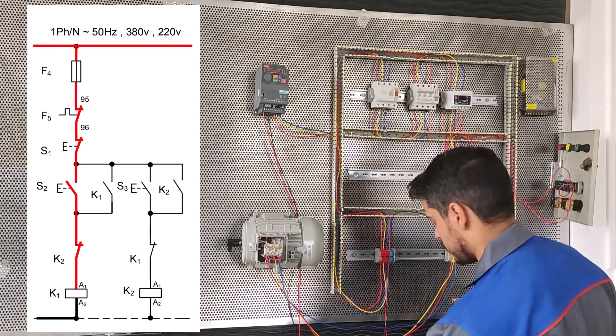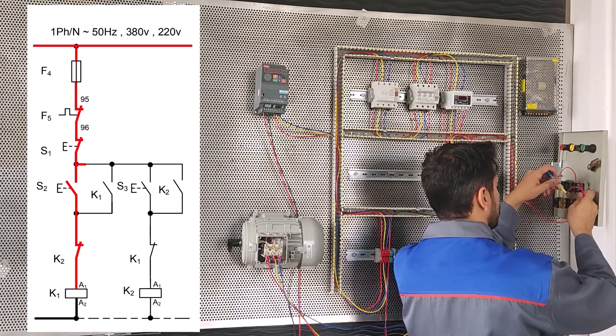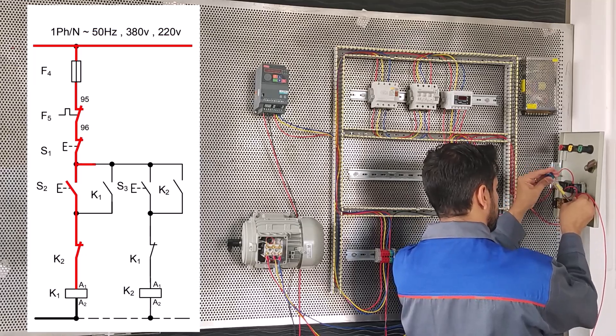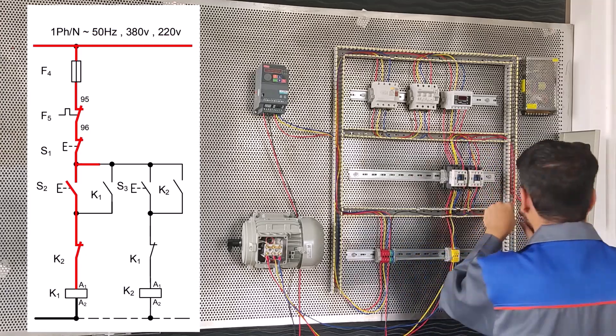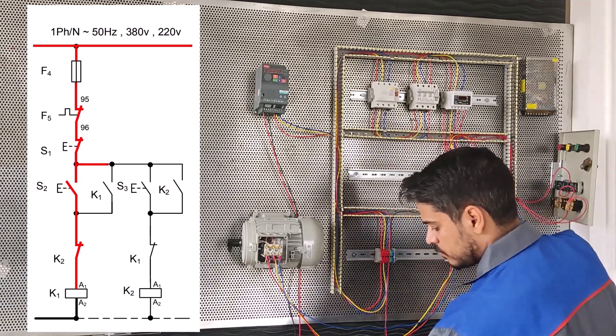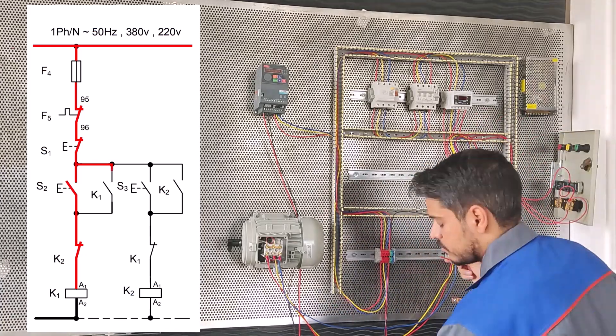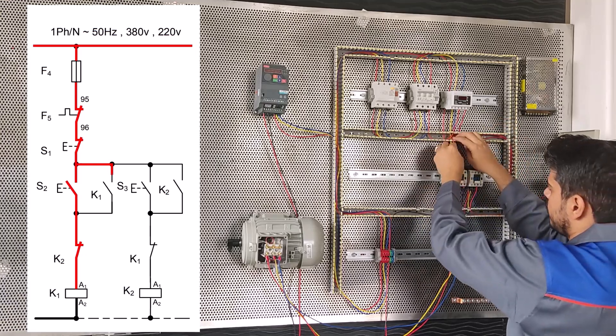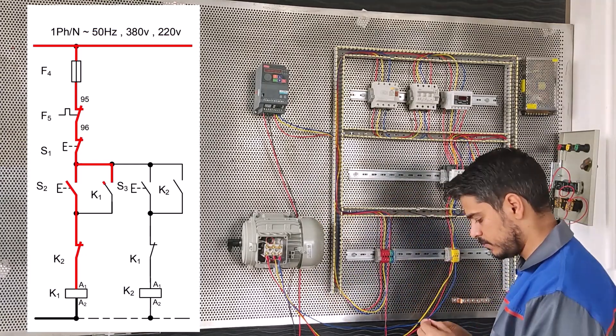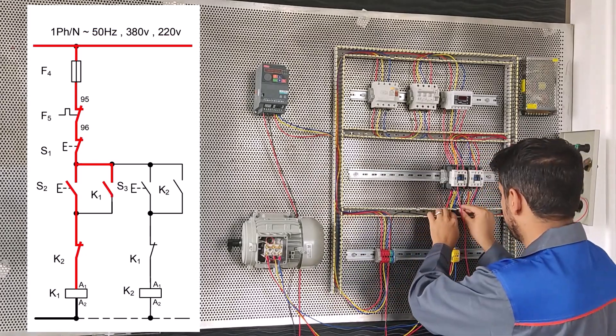And we connect A2 to neutral, or zero. Now we have to parallel 13 and 14 starter S2 with 13 and 14 contactor K1. So 13 starter S2 should be connected to 13 contactor K1, and 14 contactor K1 to 14 starter S2.